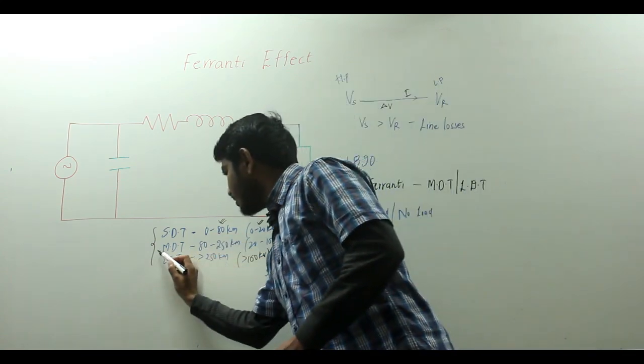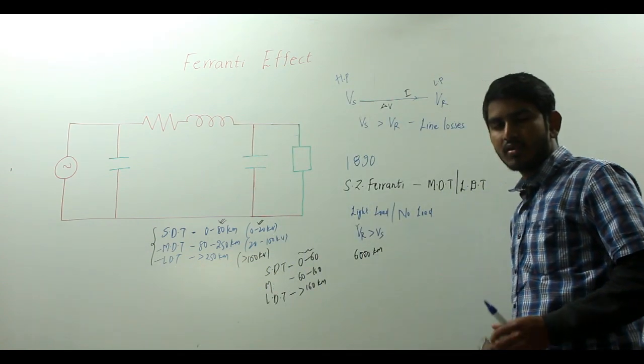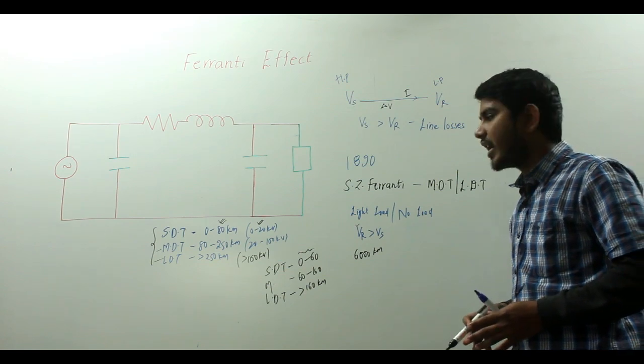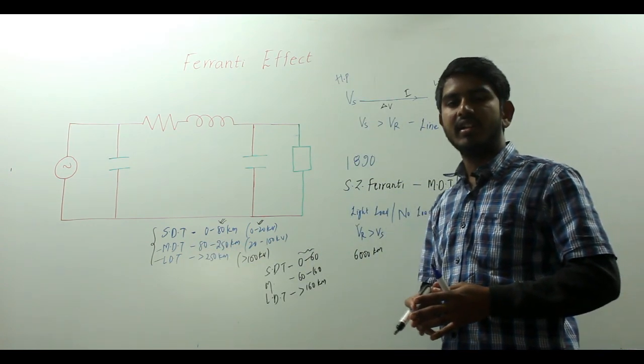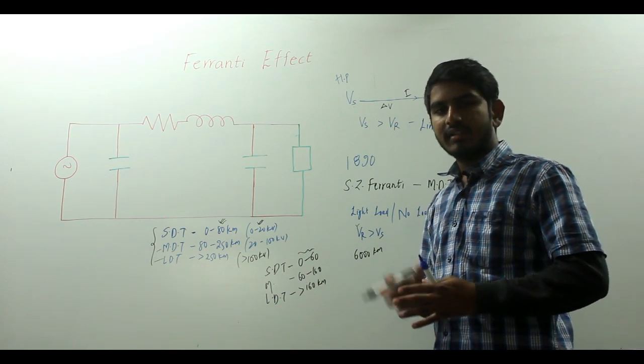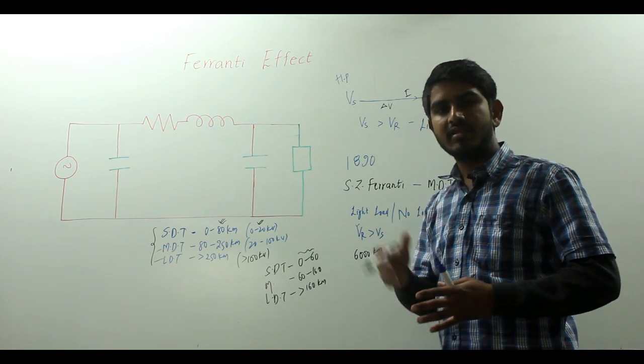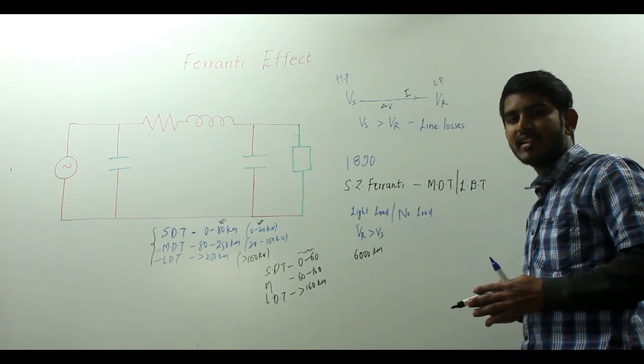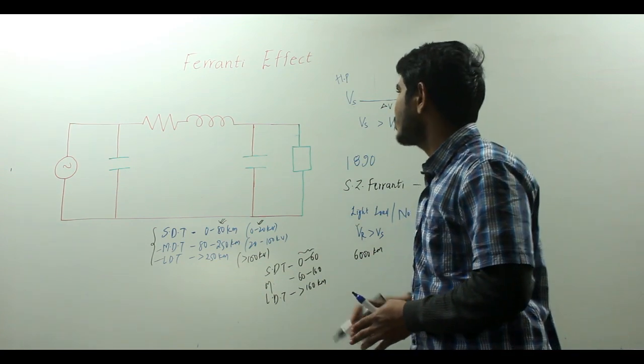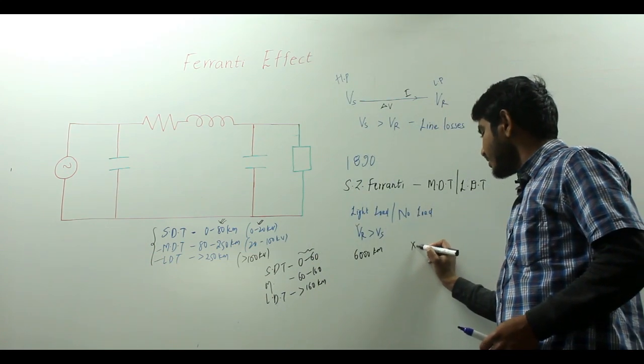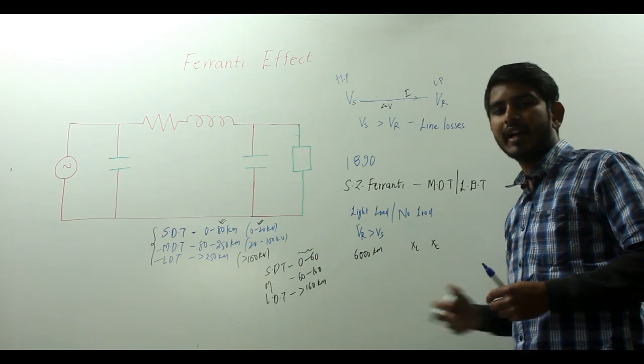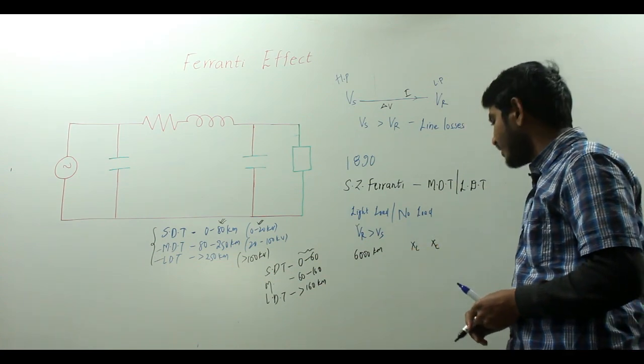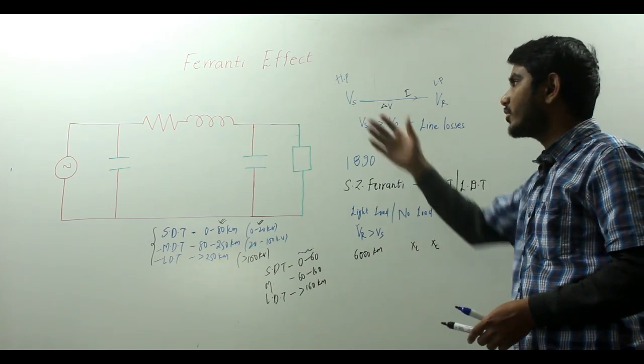The Ferranti effect occurs in medium distance and long distance transmission lines. Remember, this is very important — in interviews you must state that it occurs under light loading or no load operation, and in medium or long distance lines. The long distance transmission line inherently possesses inductance and capacitance distributed through the entire line length, and these inductance and capacitance are responsible for the Ferranti effect.